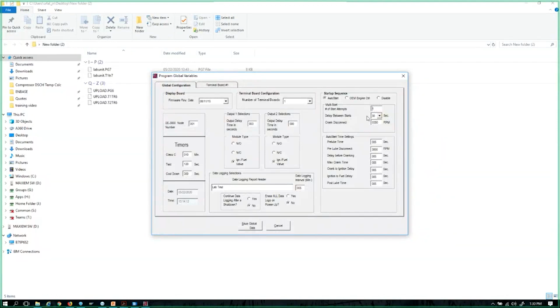Now, this is a nice feature, and we had a lot of people asking for it, but I do not recommend just going out to a site and turning this feature on if it's not designed for it. When something tries to start once and fails, a few seconds later it's going to try to automatically start rotating and cranking again. Generally in those applications we'll fit the panels or the unit with an audible and visual warning, a very loud siren and usually a strobe light. So we wouldn't ever want to activate this if the unit's not designed for it. So startup sequencing is right here.